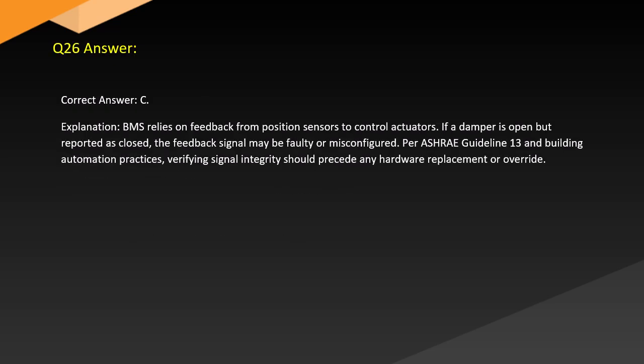Answer. Correct answer: C. Explanation. The BMS relies on feedback from position sensors to control actuators. If the damper is open but reported as closed, the feedback signal may be faulty or misconfigured. Per ASHRAE Guideline 13 and building automation practices, verifying signal integrity should precede any hardware replacement or override.